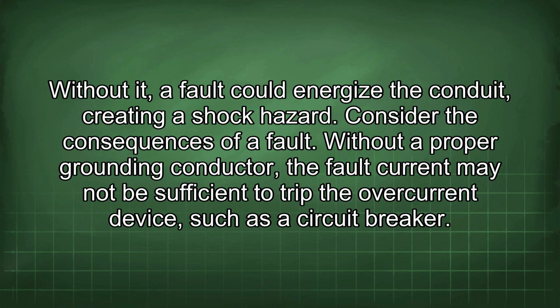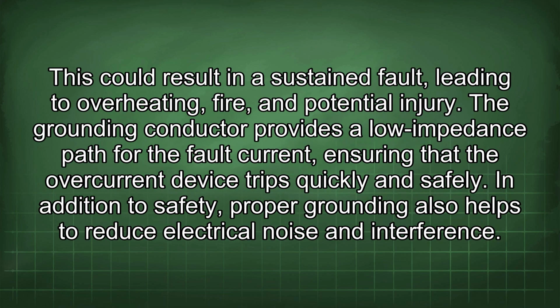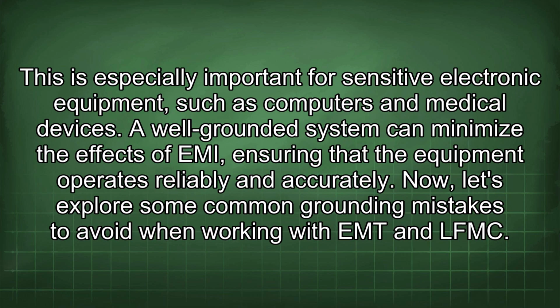Consider the consequences of a fault. Without a proper grounding conductor, the fault current may not be sufficient to trip the overcurrent device, such as a circuit breaker. This could result in a sustained fault, leading to overheating, fire, and potential injury. The grounding conductor provides a low impedance path for the fault current, ensuring that the overcurrent device trips quickly and safely. In addition to safety, proper grounding also helps to reduce electrical noise and interference. This is especially important for sensitive electronic equipment, such as computers and medical devices. A well-grounded system can minimize the effects of EMI, ensuring that the equipment operates reliably and accurately.